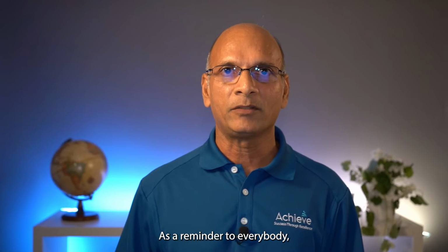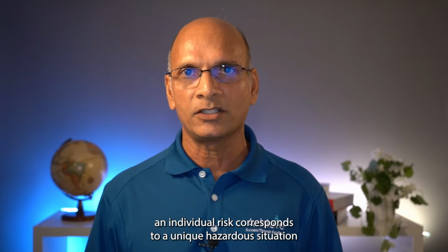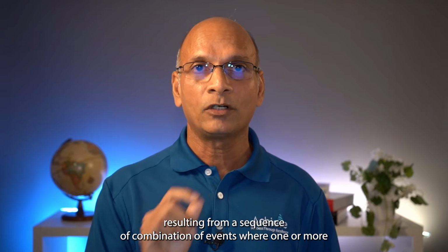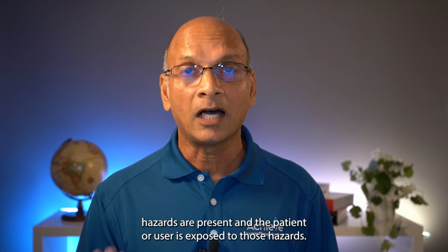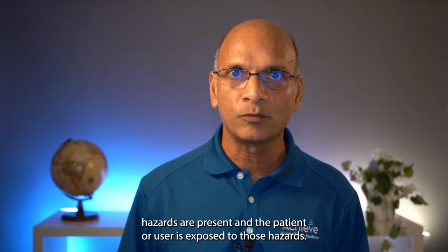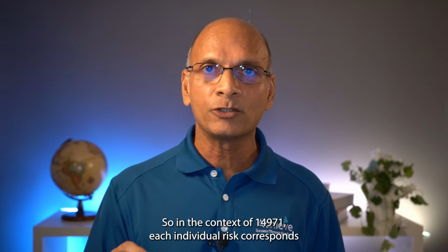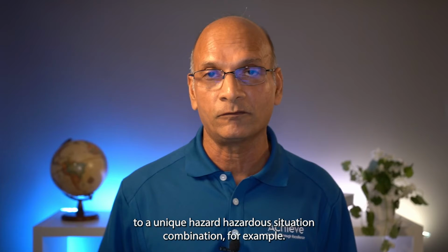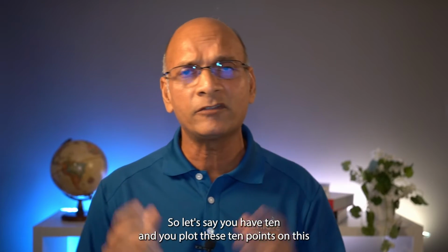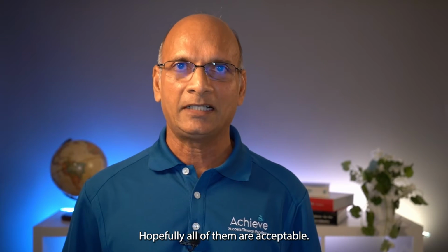As a reminder to everybody, an individual risk corresponds to a unique hazardous situation resulting from a sequence or combination of events where one or more hazards are present and the patient or user is exposed to those hazards. So in the context of 14971, each individual risk corresponds to a unique hazardous situation. So let's say you have 10 and you plot these 10 points on this 5 by 5 grid. Hopefully all of them are acceptable.